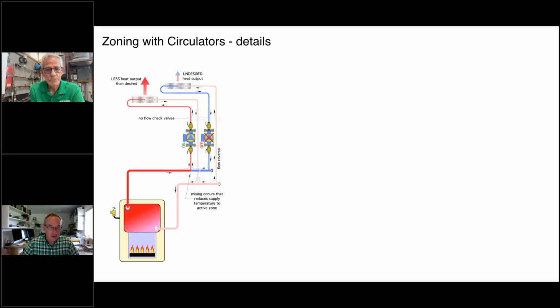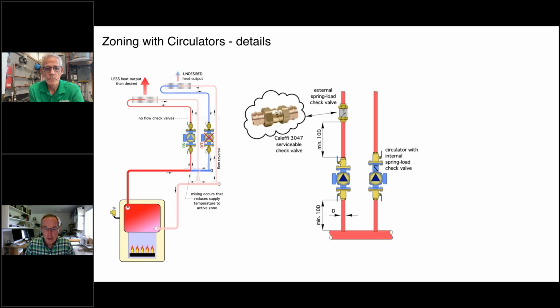So if you take this and just extend it to 3, 4, 5, however many zone circulators, the general idea is it's really simple. You need a check valve in each one of those. And there's a couple ways you can do it. Over here, we're showing the internal check valve. Most of the circulators that are sold today as zoning circulators, common ones, Taco 007, Grundfos 1558, so forth, come with internal check valves that just slide into the volute. But Caleffi actually does make a nice serviceable, and that's a key word there, it's a serviceable check valve, meaning that you can open these unions up, and if something did get clogged or jammed into the mechanism in there, you could clean it out, put it back in.